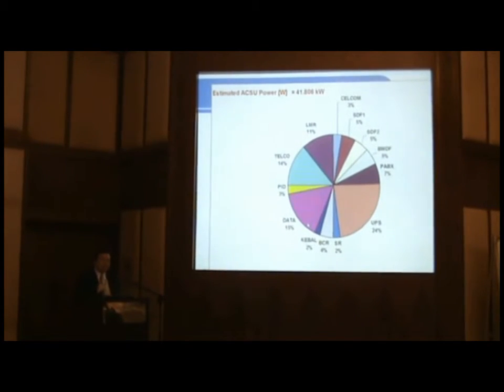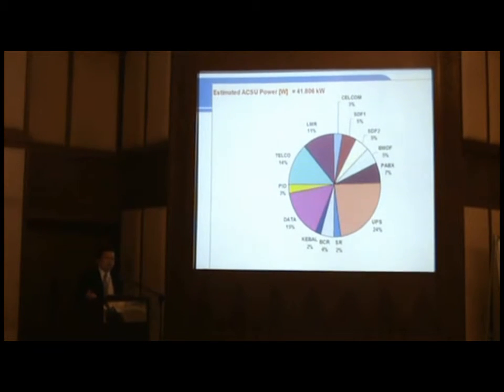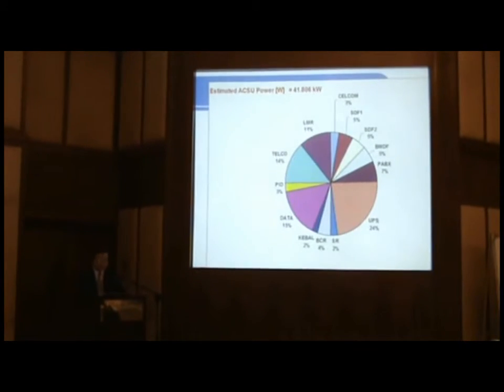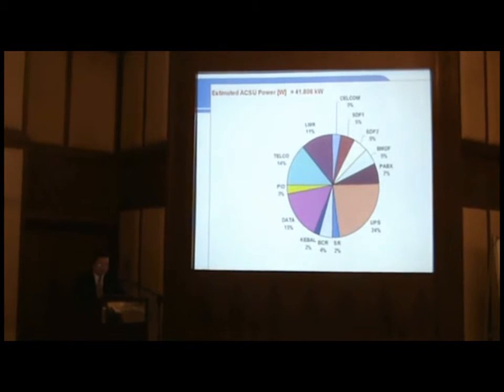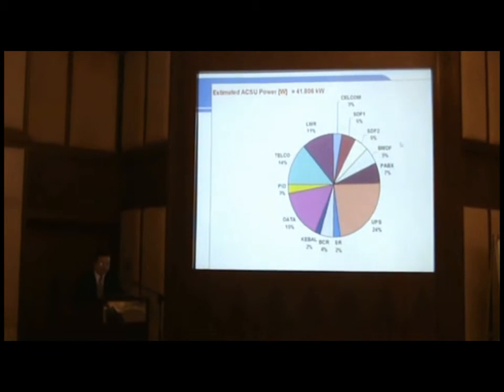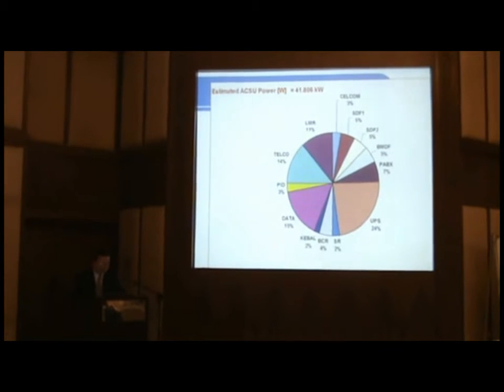Rule of thumb: if your IT equipment load is, say, 10 kilowatt, your cooling system should not be designed for 10 kilowatt, it should be less. Because some energy used will be converted partly to heat, but if it's more than that, it means some other heat is coming in, so it's not just cooling the equipment but also cooling what we call ghost load, which we won't be able to measure.